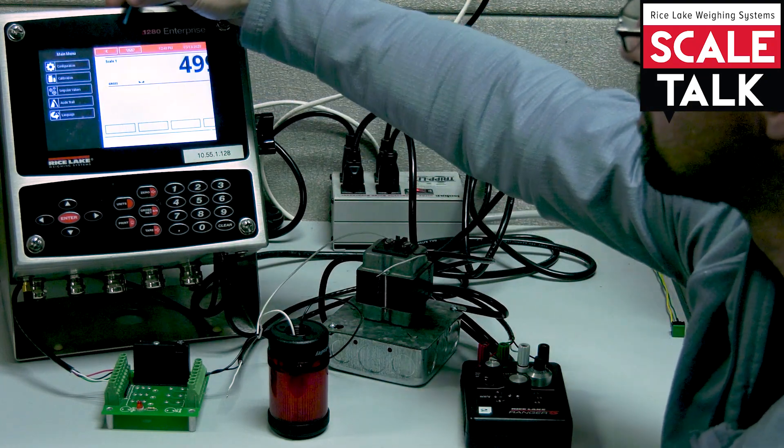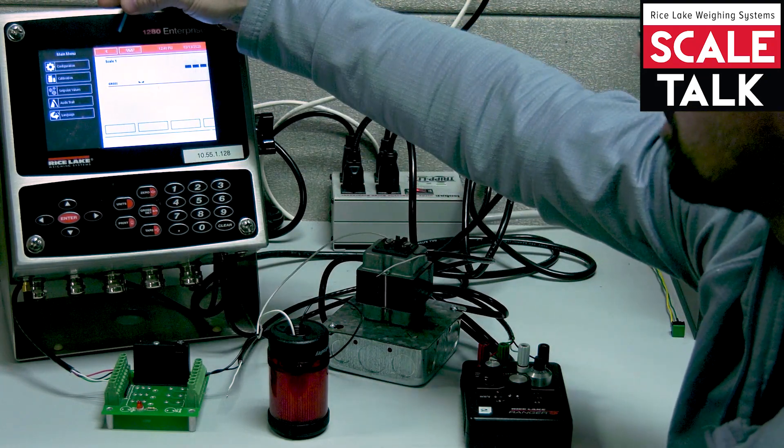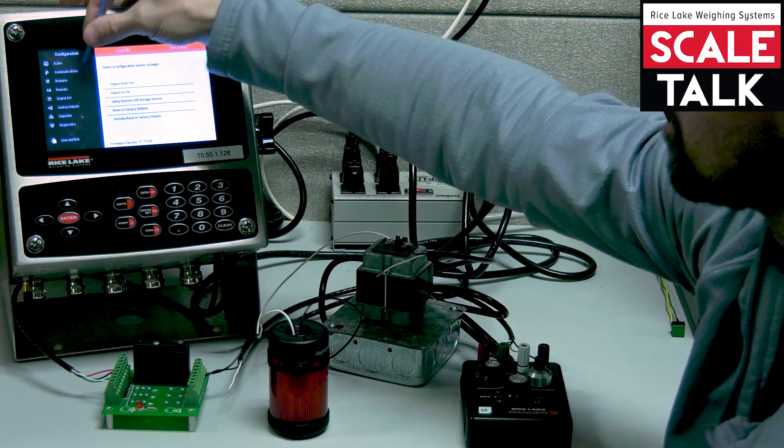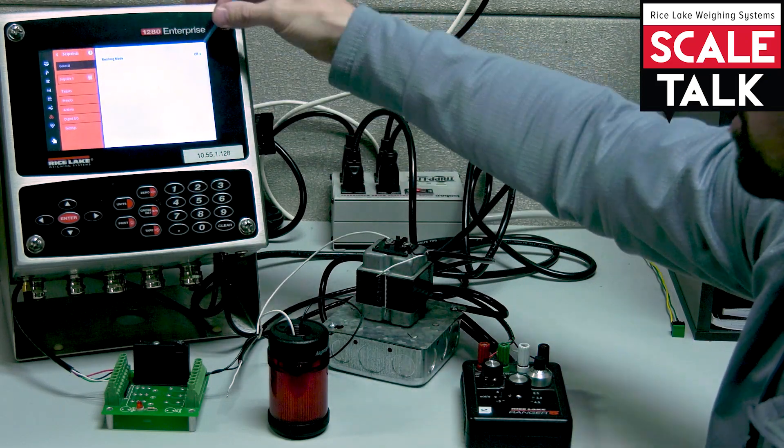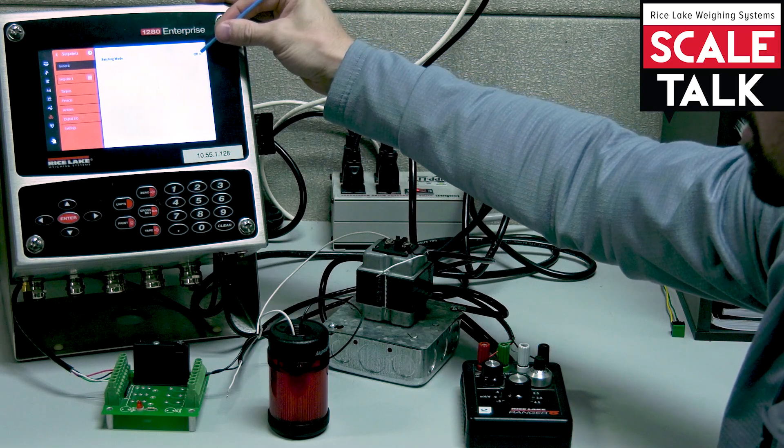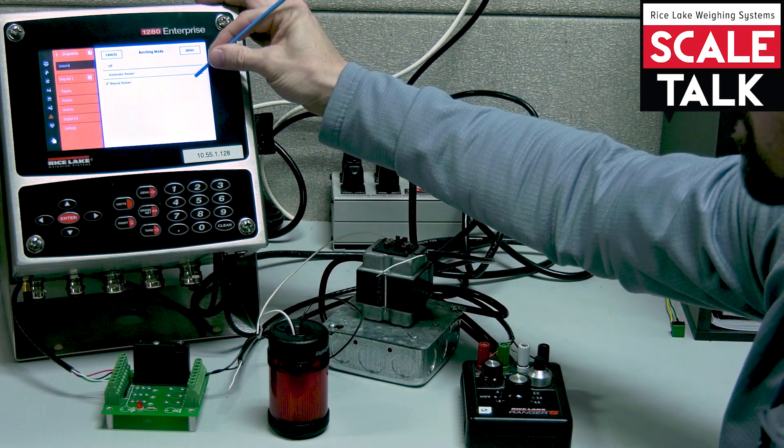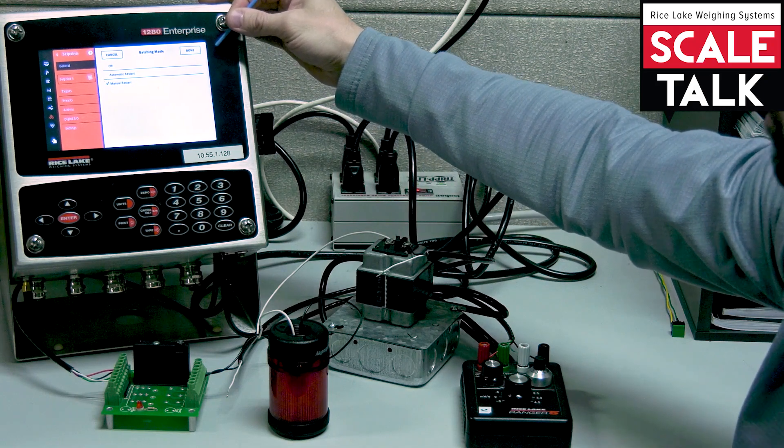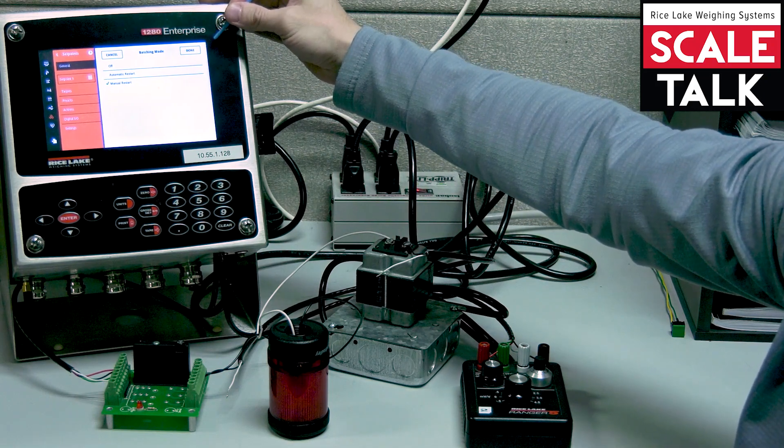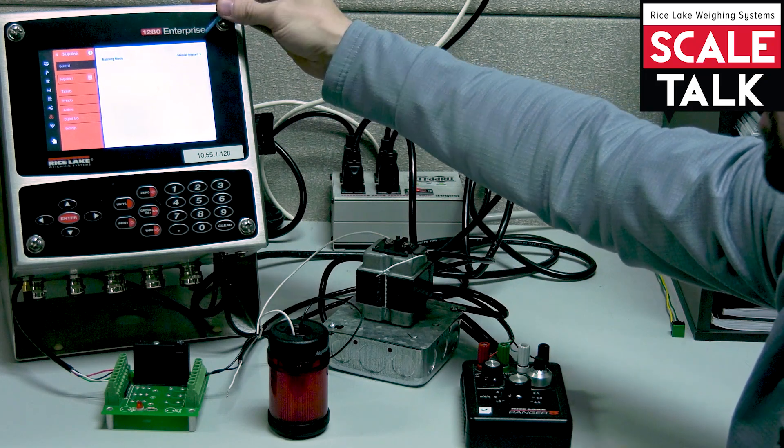Hop back in the menu. Go into config. We'll come down to our set point menu. We're going to go ahead and turn our batching mode on. We'll set it for manual restart. And that just means that somebody has to tell it when to go each time a routine is run. Select done there.